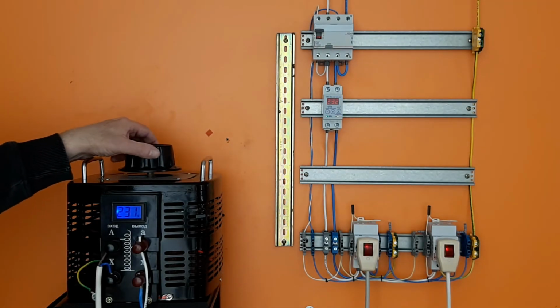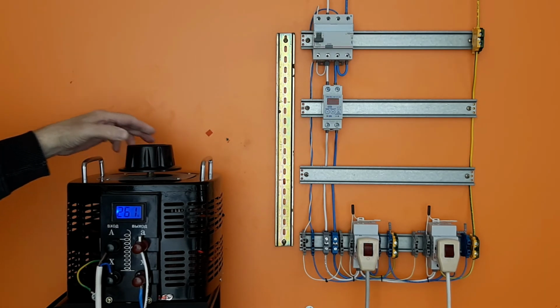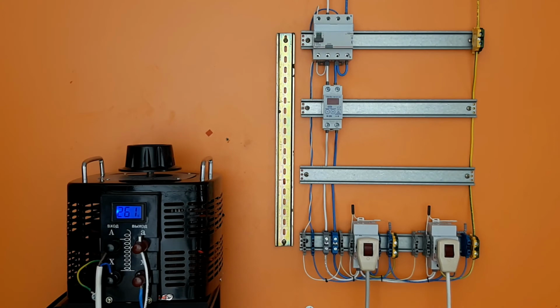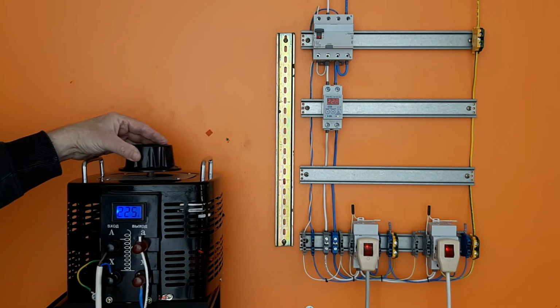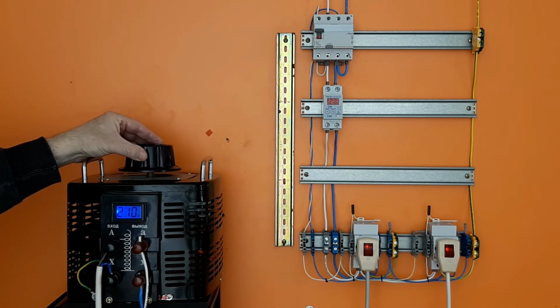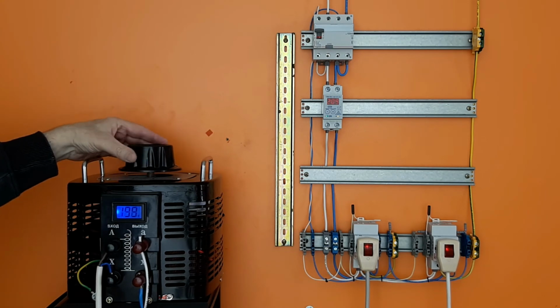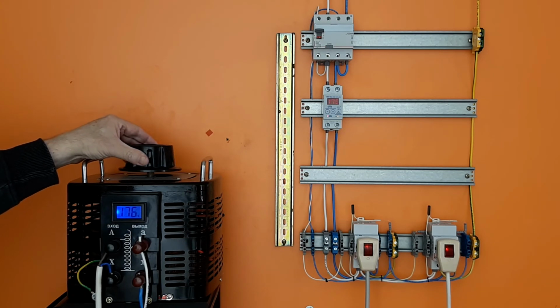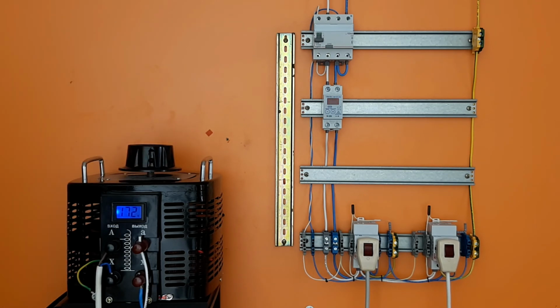Another useful property is found in a link with a voltage relay. Let's see, when the voltage increases, an interruption occurs at the set limit. The differential current device is triggered simultaneously because it has registered a line break. The same thing happens when the voltage is lowered. Since the voltage relay is located after the differential current device, automatic reactivation is excluded. If you remember, we used to achieve this effect differently by swapping the relay inputs and outputs. If desired, automatic reactivation can be maintained. For this, the relay must be located before the differential current device.